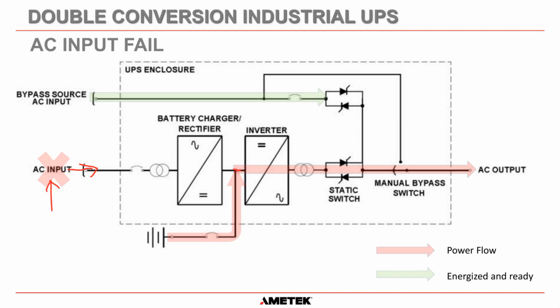And you'll notice that the inverter stays on because the inverter is the most reliable form of power we have, because we know that this inverter, if it is a single phase system, will give us 120 volts AC. It's a beautiful sine wave that is regulated at 60 hertz and everything will be fine. Okay. And then the power flow is just the same as it was in the previous slide from the inverter onwards. Now, some people say, well, wait a minute. It's only this MCC that has gone out. We still have our bypass source available. Why don't we transfer to bypass and save the batteries? That's a very good question.